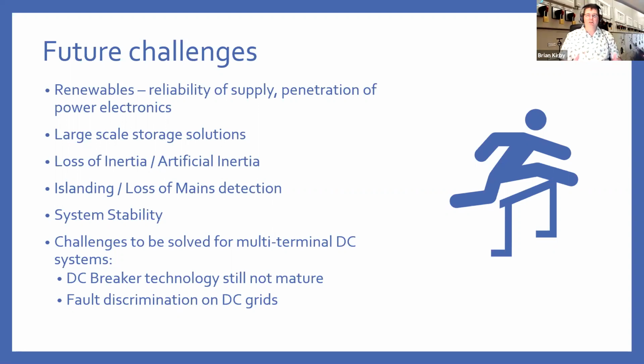And then multi-terminal DC systems, breakers is still not mature. There's lots of fanfare out there, but they still haven't really got to that maturity level that's required for this to become feasible. And fault discrimination on the grids as well, because if you've got a fault on a DC grid as opposed to a point-to-point, you don't want to switch the whole network out. You want to be able to isolate just portions of it.